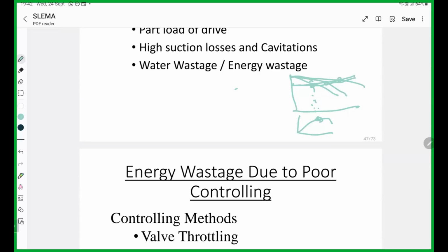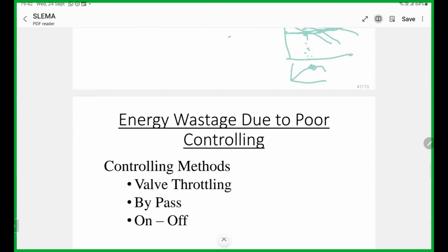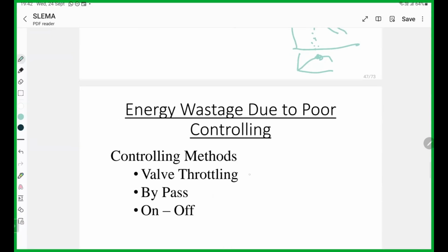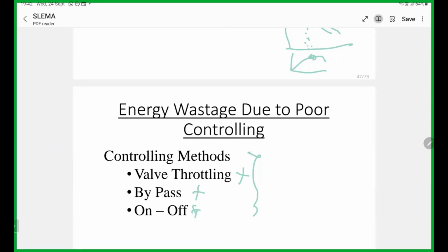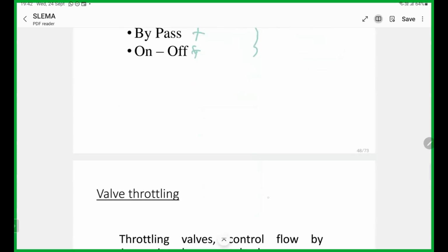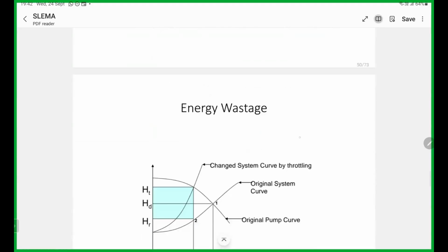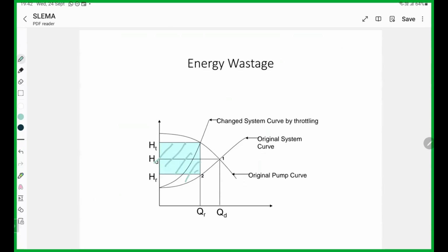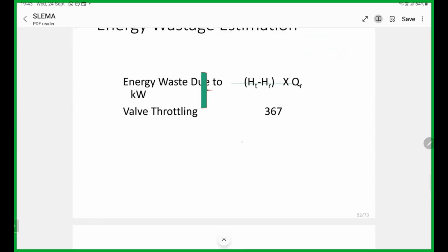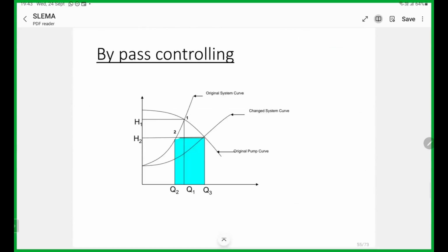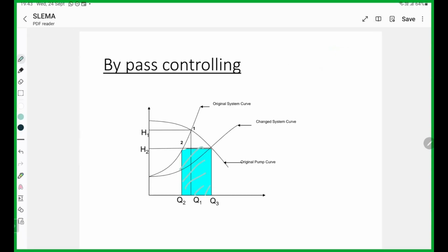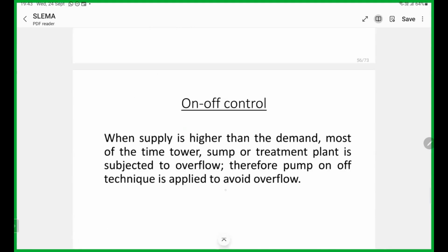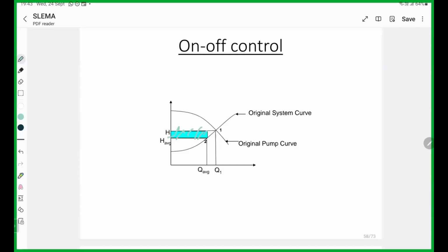For a steep system curve, VFDs are ideal, and VFD or impeller trimming. Then control valve throttling is an energy loss. Bypass is also an energy loss. On-off is also an energy loss. These control methods are not recommended in terms of energy conservation. If you throttle the valve, you lose this amount of energy. If it is bypass control, you lose this amount of energy. If it is on-off control, you lose this amount of energy.